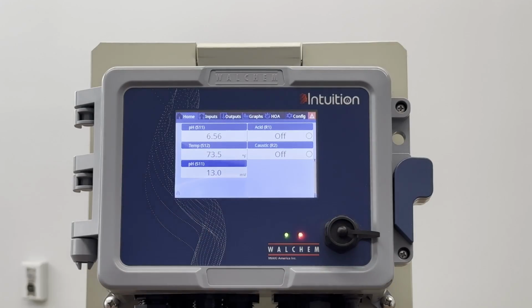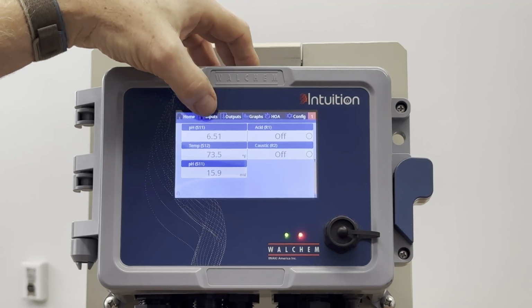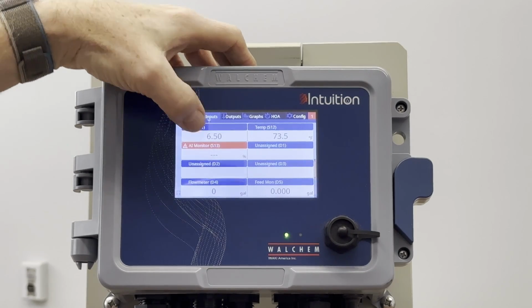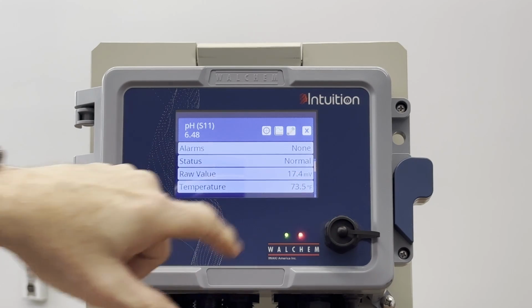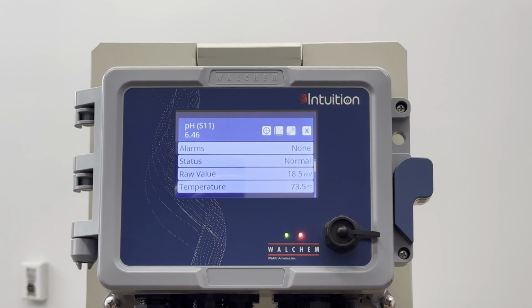And a good indication of that is the millivolt readings, even before you do the calibration. If you look at the millivolt readings of a sensor, and if you didn't have it on your front screen, you can go to inputs, you can go to pH, and it'll show you the raw value of the sensor. So right now I'm in tap water and I'm reading 19 millivolts approximately. The way this works is theoretically there should be about 59 millivolts per unit from 7, and it's opposite of what you'd think. As you go down, it's a positive number. As you go up, it's a negative number.